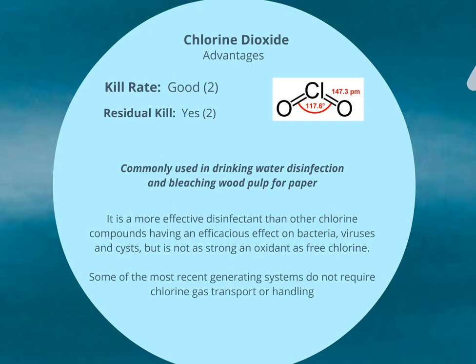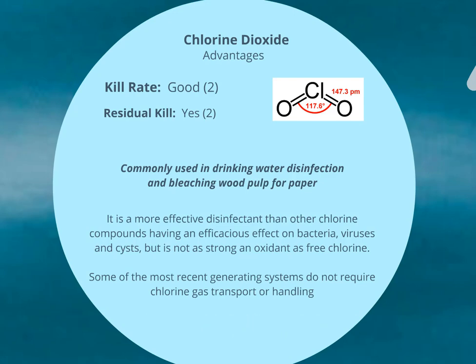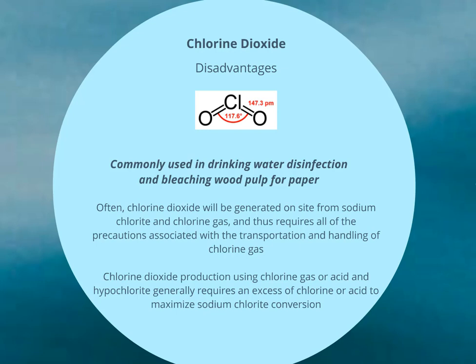Chlorine dioxide has a good kill rate and also has residual kill after application. It's very effective — more effective than chlorine — but it's not as strong an oxidant as free chlorine. Some of the most recent generating systems do not require chlorine gas transport or handling, which makes it safer. However, it's often generated on site and requires all the precautions associated with the transportation and handling of chlorine gas. Chlorine dioxide production using chlorine gas or acid and hypochlorite generally requires an excess of chlorine or acid to maximise sodium chlorite conversion.